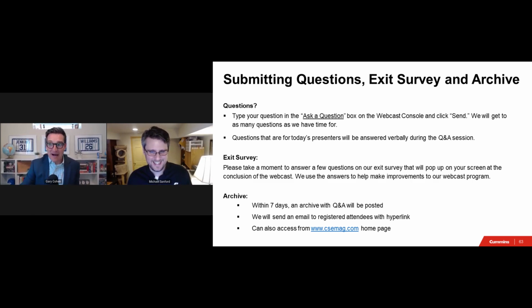How far away is Cummins from hydrogen engines, and what's Cummins doing to increase step load performance of gas and hydrogen engines? One of the biggest challenges we see with hydrogen today is energy content, a similar challenge we face with diesel and natural gas engines. For reference, Cummins' QSK60, a 60-liter diesel engine, produces 2.5 megawatts of power. To reach 2 megawatts on natural gas, we're using a 78-liter engine. That comes down to energy density and the ability to combust that fuel.